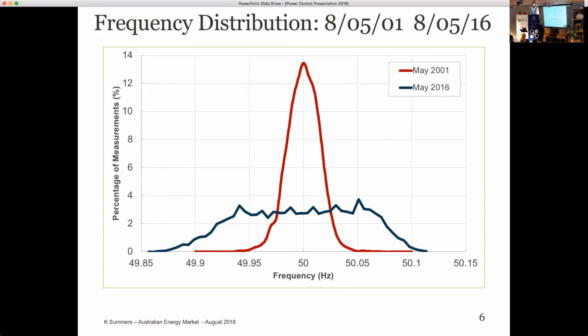Now, if you examine a histogram, where the shoulders are, it tells you where your primary control commences. When you have that, you're seeing primary control actually active. When you're seeing this, you're seeing a version of, well, there is some control there, but it's sort of a long way out. So this is our new frequency standard. Anywhere between here to here, we say it's okay for the power system to operate. That's our normal operating frequency band.